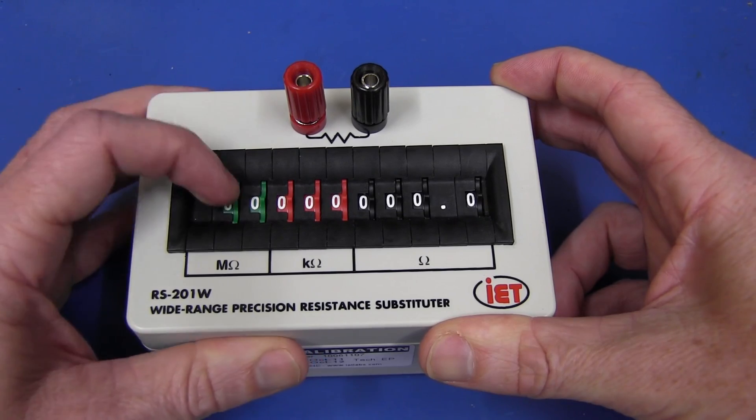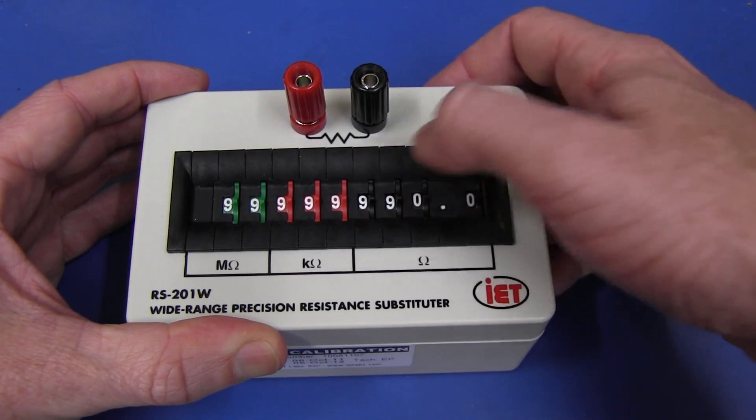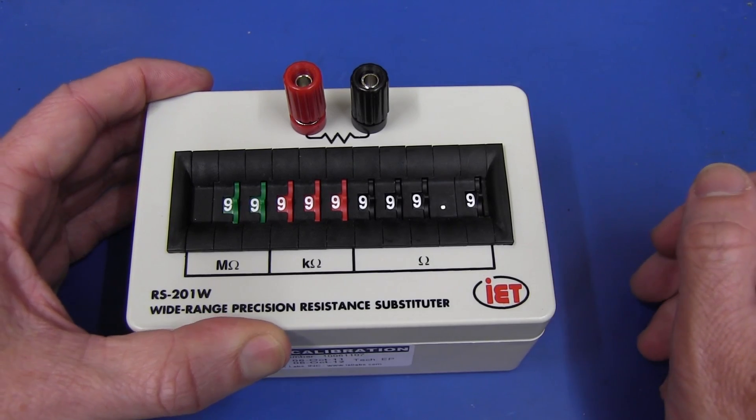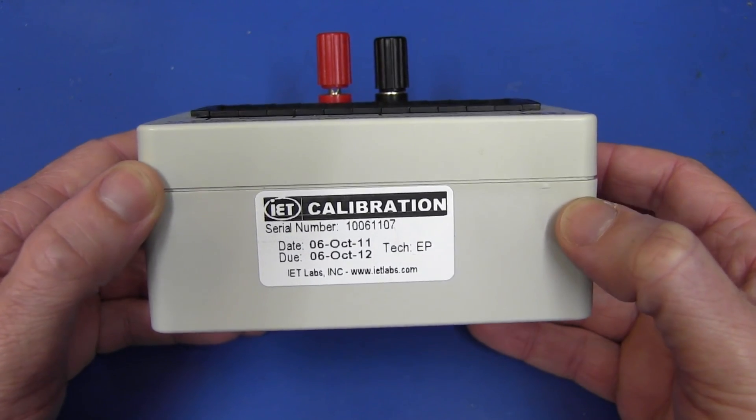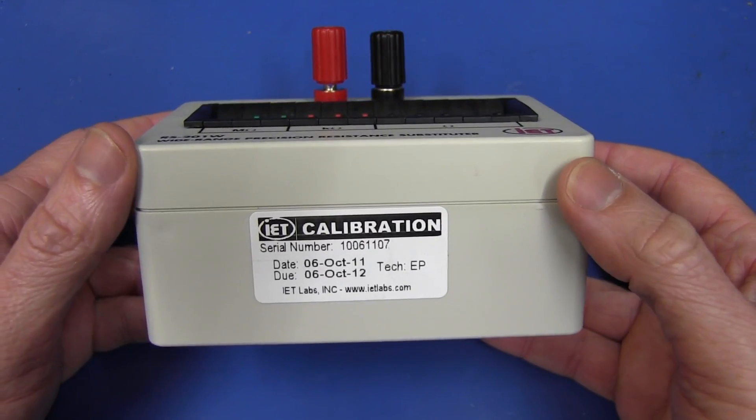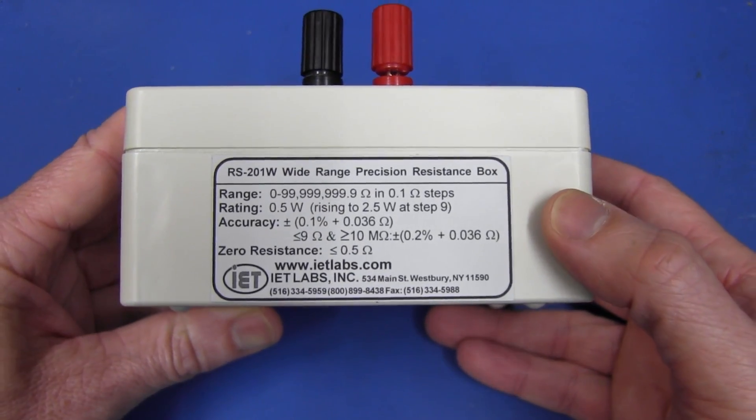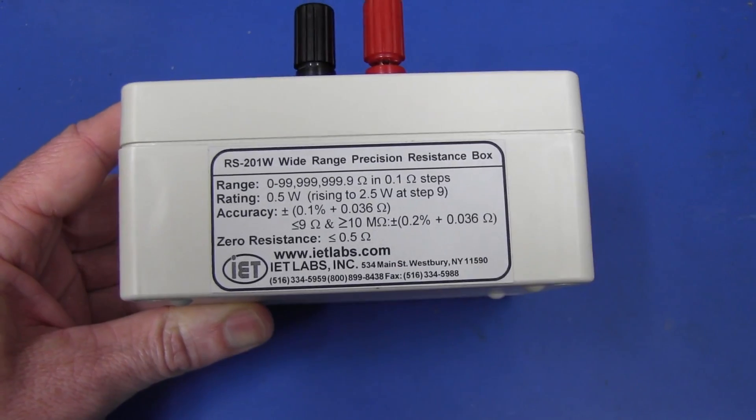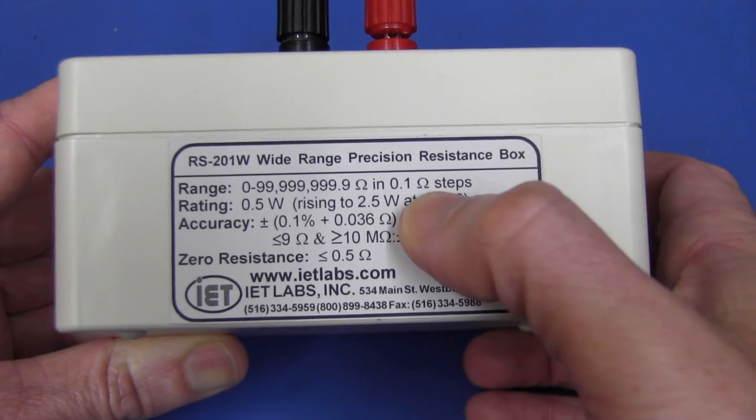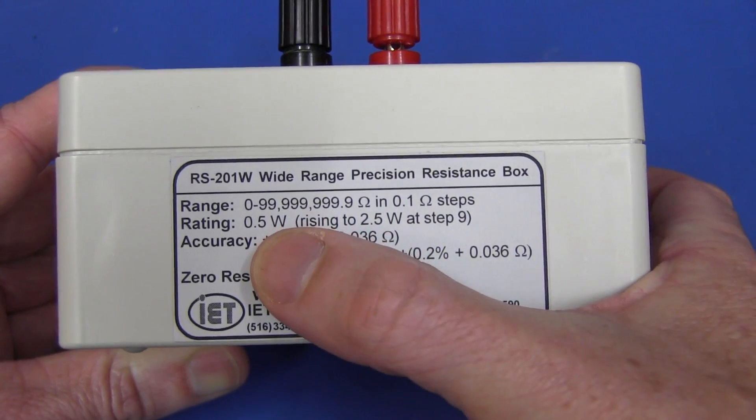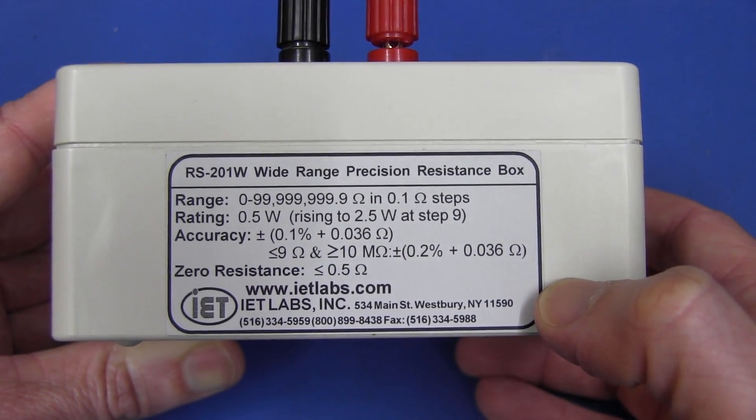And it's nine decades. And we can dial in any value up to 99.9999999 megohms. Crazy. Now this one is actually calibrated, so it comes with a calibration certificate. That's an extra $74 if you want to get it calibrated. But they give you a full test report we'll take a look at. Here's the specs from zero to basically 99.9 megohms. As we said in 0.1 ohm steps, it's a 0.5 watt rating. So each resistor inside will be 0.5 watts.